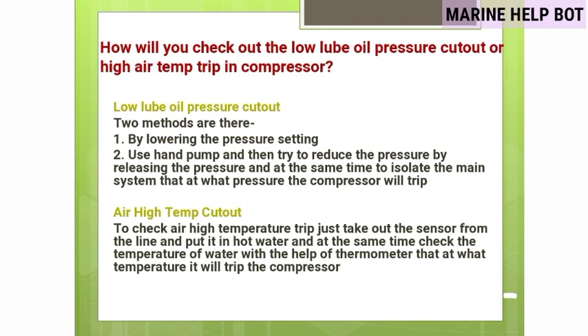How to check low lube oil pressure cutout: either lower the pressure setting, or use a hand pump and reduce pressure by releasing it while isolating the main system to observe at what pressure the compressor trips. How to check air high temperature trip: remove the sensor from the line, place it in hot water, and simultaneously check the water temperature with a thermometer to observe at what temperature the compressor trips.